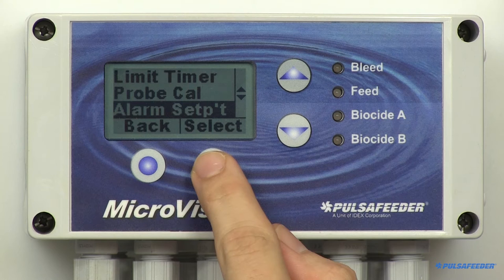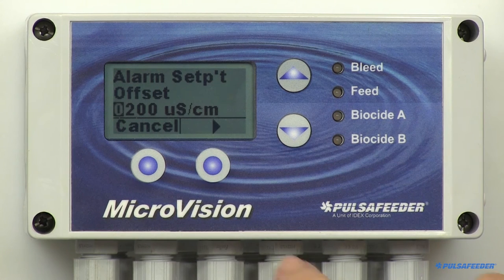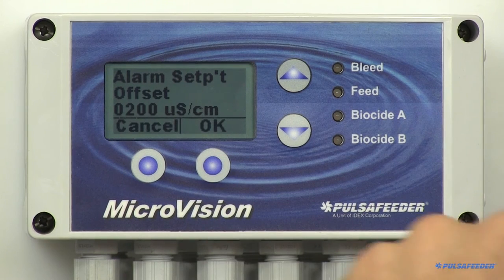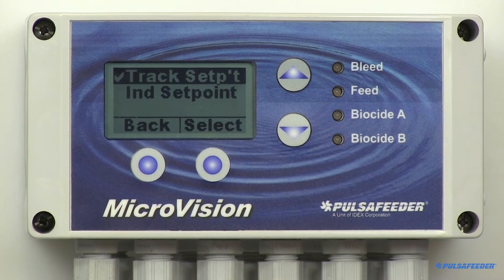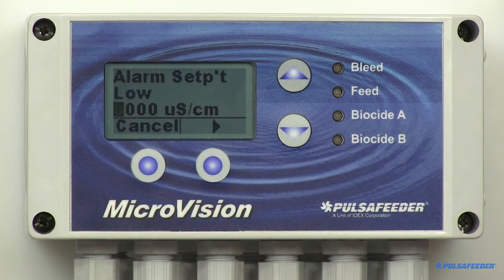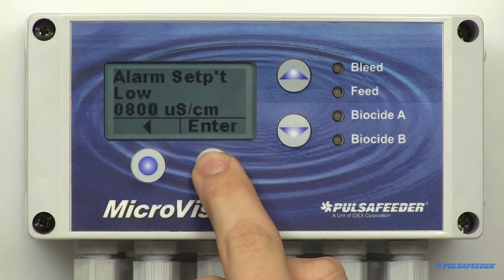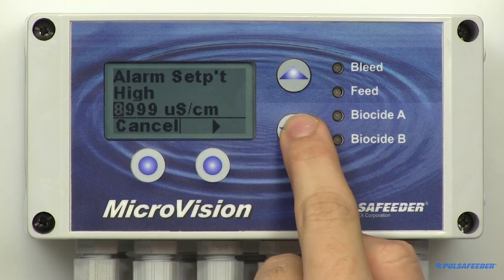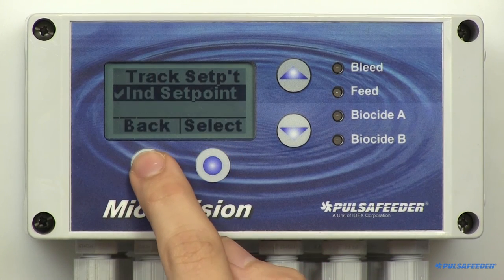From the conductivity menu, arrow down to select Alarm Setpoint and press Select. The Track Setpoint is already highlighted, so select it. Simply enter the value here using the arrow buttons, then hit Enter and OK. This one value is used for both the above and below alarm setpoint. The other alarm type is Independent. Arrow down to Independent Setpoints and select it. Use this type if you want to specify a different upper and lower conductivity value for alarm reporting. The first screen is the low value — enter it using the arrow buttons and hit Enter and OK. Then the high screen value will appear; enter it using the arrow buttons and press Enter and OK. Then press Back to return to the conductivity menu.